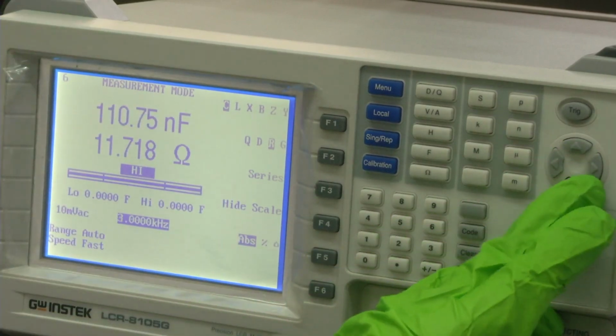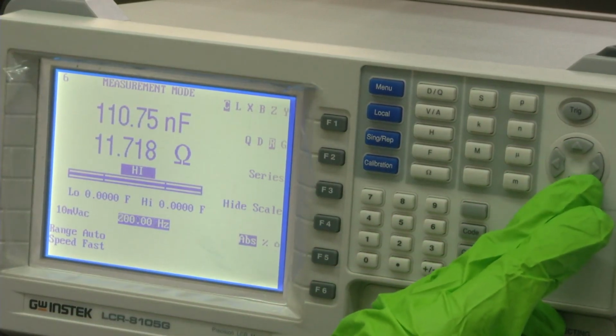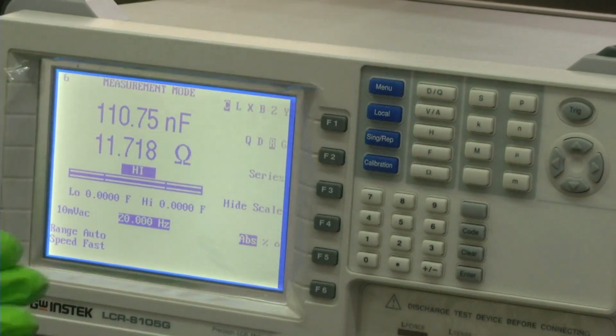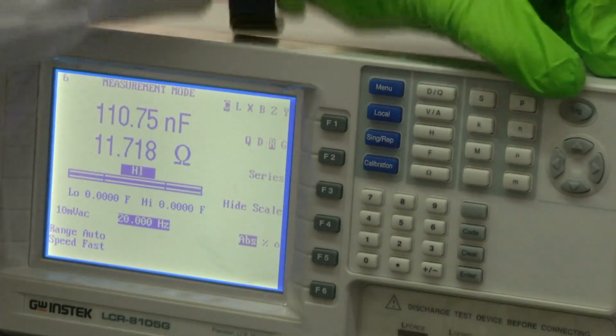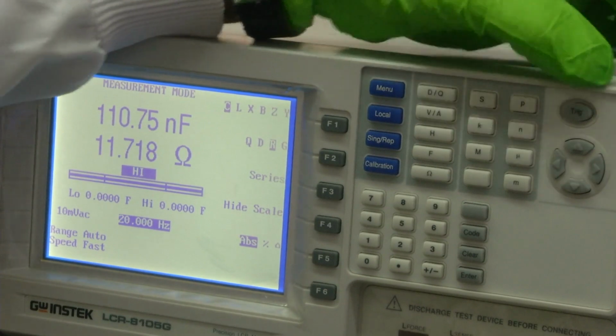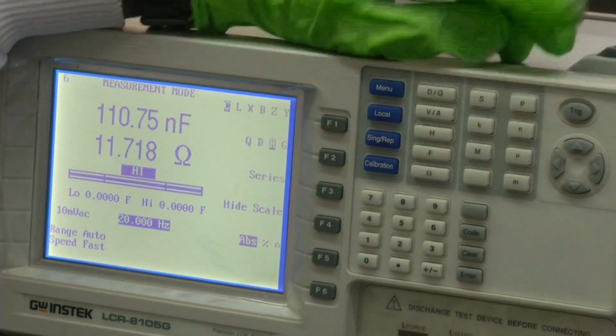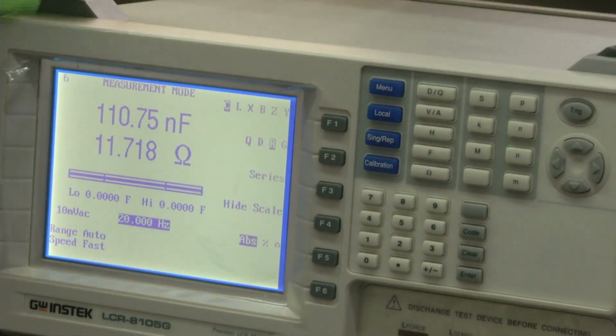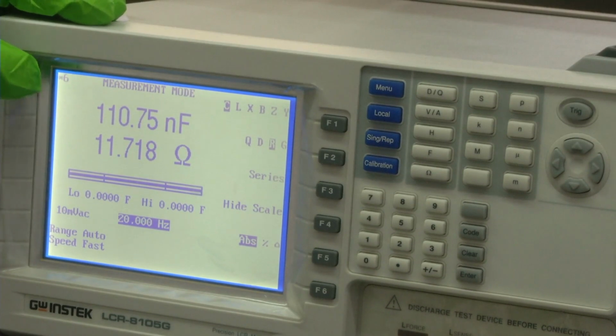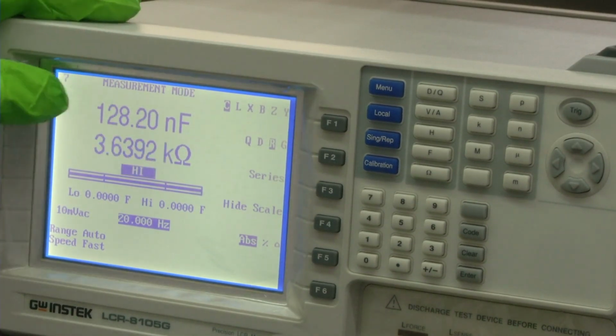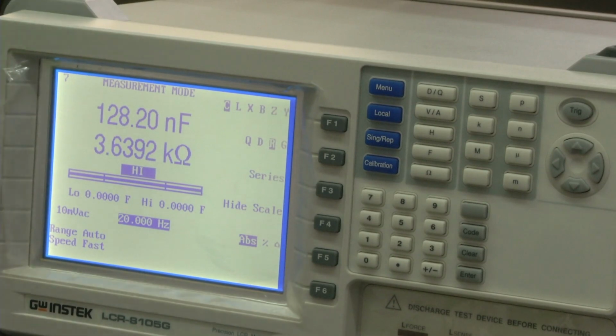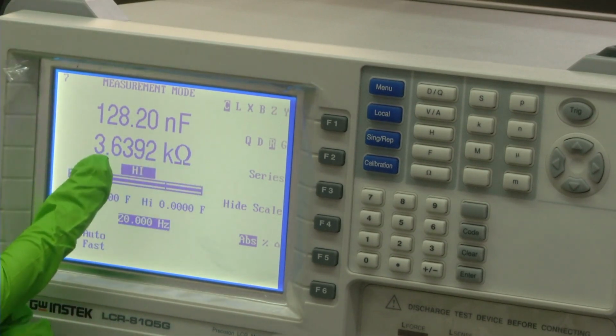Every time we change the frequency here, let us go to a very low frequency, let us say 20 hertz. Every time we want the equipment to measure these individual values, we have to click trigger. This is the trigger button. When you click trigger, you can again see the capacitance value is almost roughly in that range of 0.1 microfarad, but see the impedance, it has become 3.6 kilo ohms.